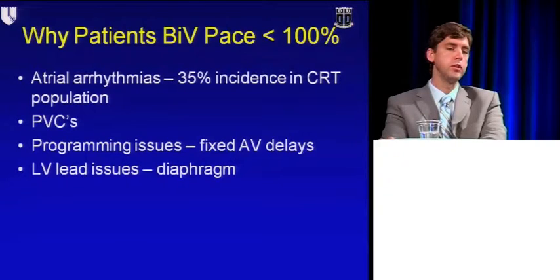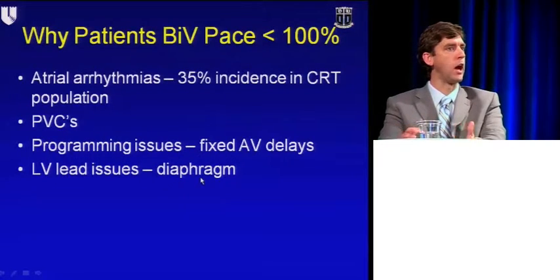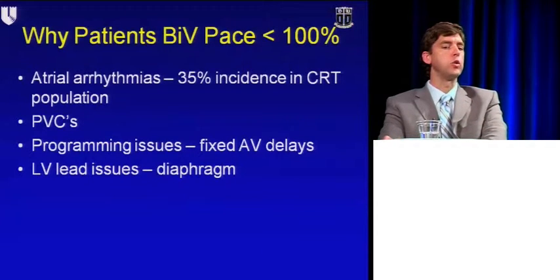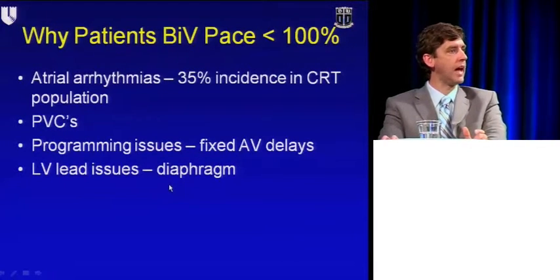There's programming issues. We oftentimes have fixed AV delays. We program them out of the box. We don't account for when they atrial pace, and we have to adjust the AV delays, or they exercise and the AV delay doesn't shorten appropriately. And so they will start to beat out the pacemaker. BiV pacing will go down. And then less frequently now, there can be lead issues where you can't actually use the lead you put in because it's pacing the diaphragm or the threshold is very high.